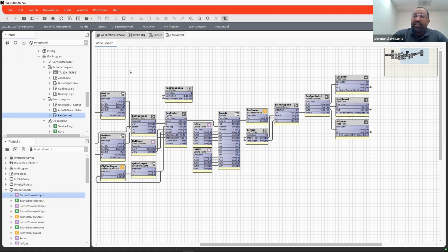I want the stage heat to come on, and basically if I turn on stage 1 and my discharge temperature goes up to 85 degrees, then go ahead, simulate stage 2 and see if I can drive my temperature up to 90 degrees.